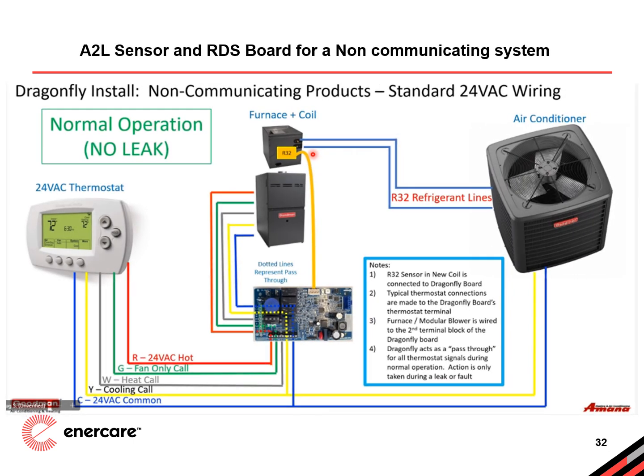Pictured is how a traditional 24-volt control system and sensor would be wired for safe A2L operation. The sensor is provided within the coil and the Dragonfly board is field installed. The control essentially sits idle unless there is a fault sensed, whether that is a refrigerant leak, control, or internal sensor fault.